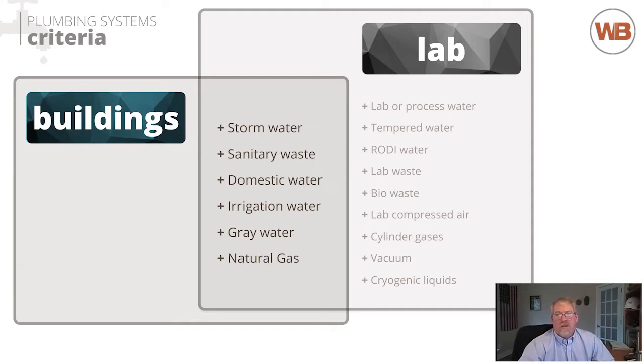The one thing I like to say in your master plan, and we talked about that responsibility matrix earlier, you need to start defining what you're going to provide as a landlord. And as a tenant, you need to look towards what you're expecting from the landlord. Are you expecting, for example, a pre-treatment water skid with particulate filter and softener, and tenant-by-tenant water treatment for RO, DI, USP, or whatever you might need? That will drive the strategy for leasing, the strategy for physical space, and how much space you'll need to lease.